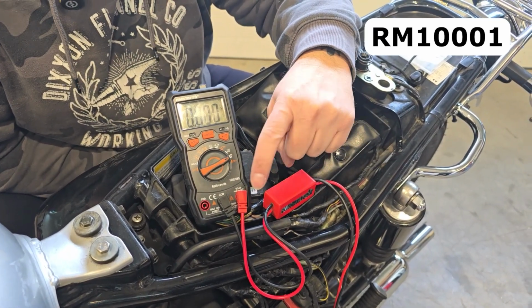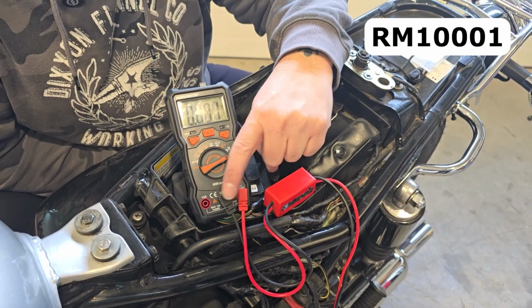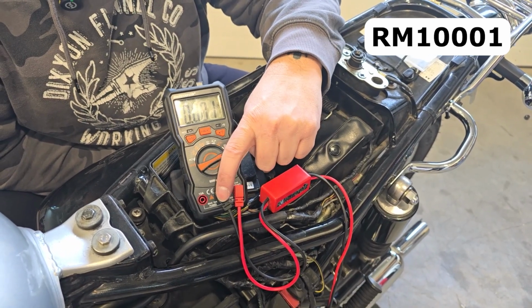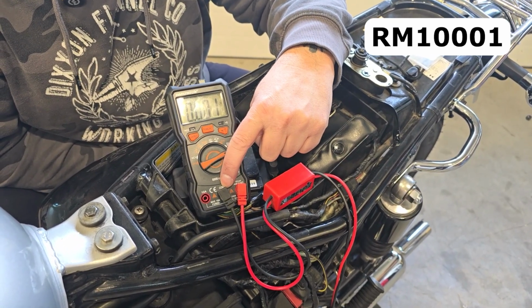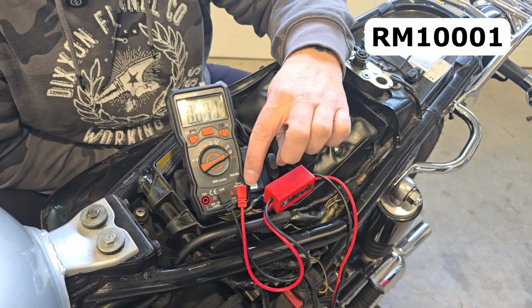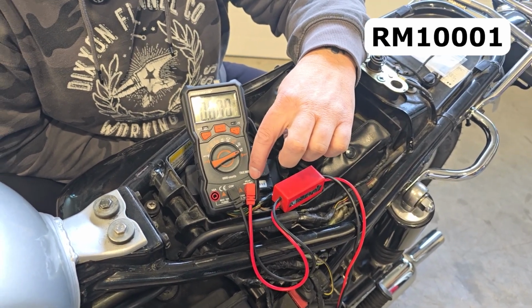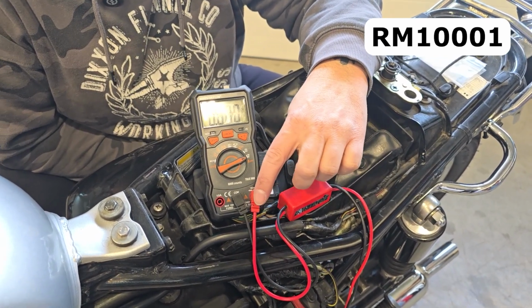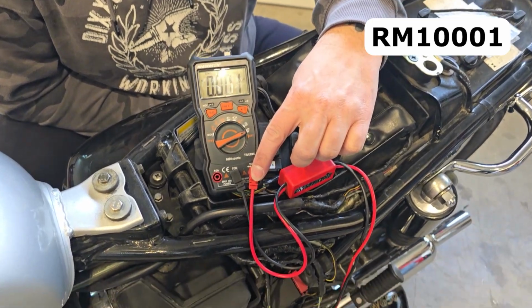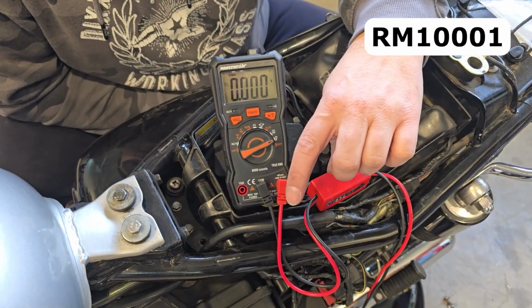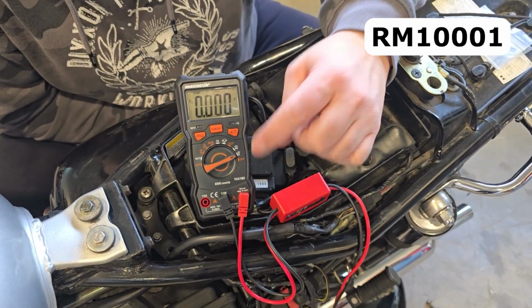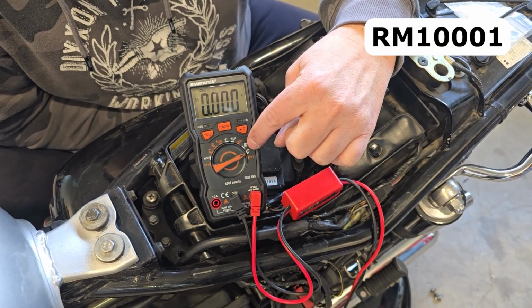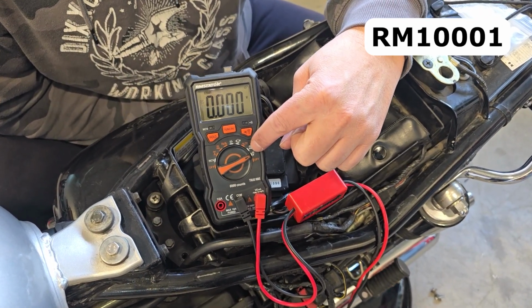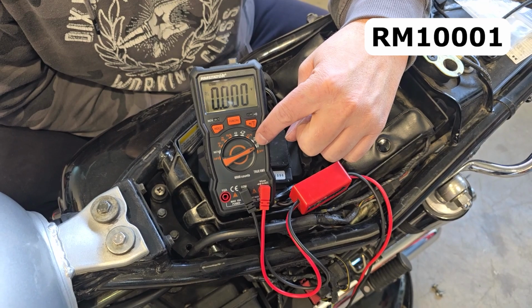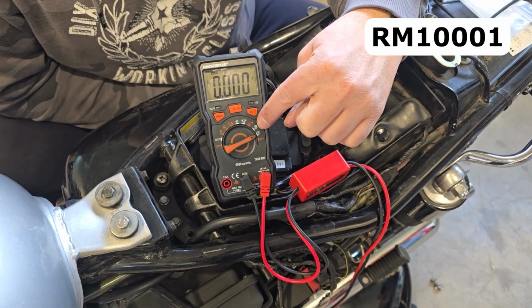You will connect it to your meter, first of all, to the same terminals you typically use. The black will go to common or ground in the center, usually, on most meters, and the red will go to the volt, resistance and continuity terminal, usually on the right side of your meter. I can't say that's true for everyone, but most meters are set up this way. Then turn your dial or selector to DC voltage. I've seen confusion online about that: you definitely are measuring DC voltage.